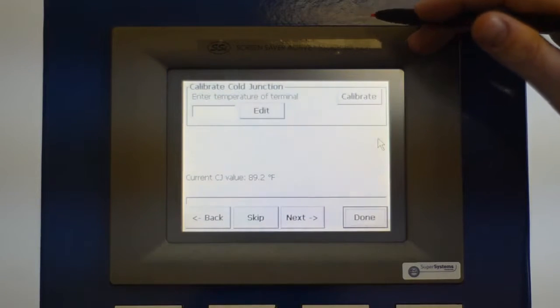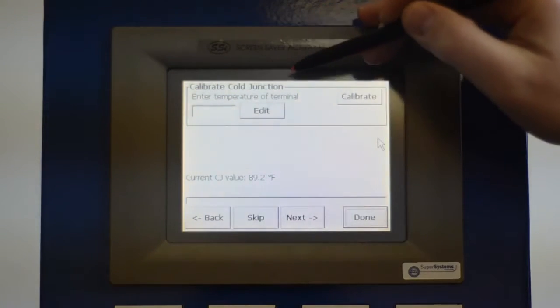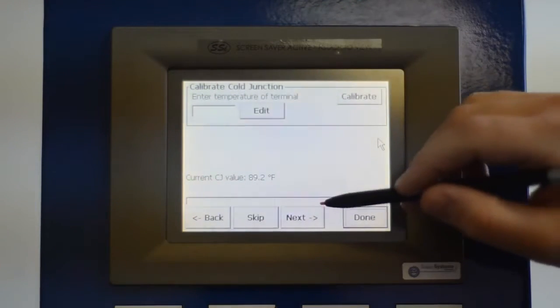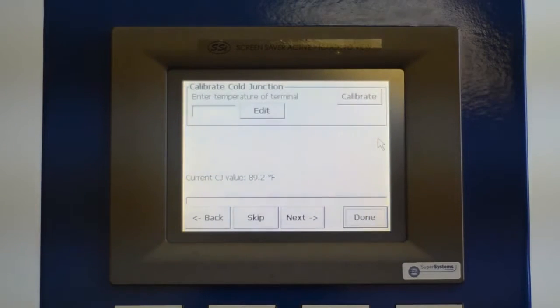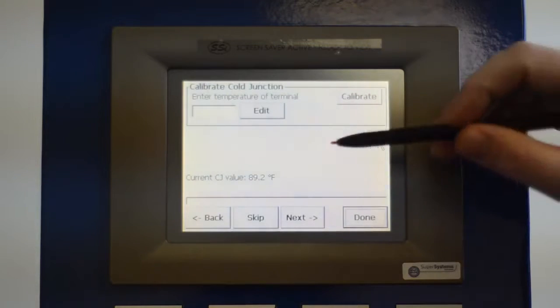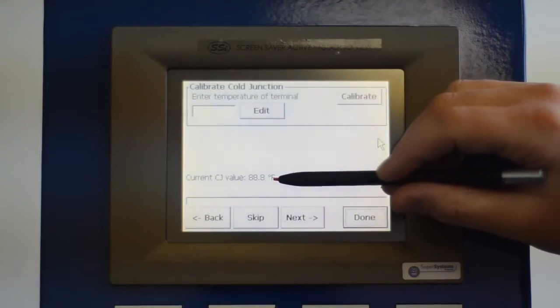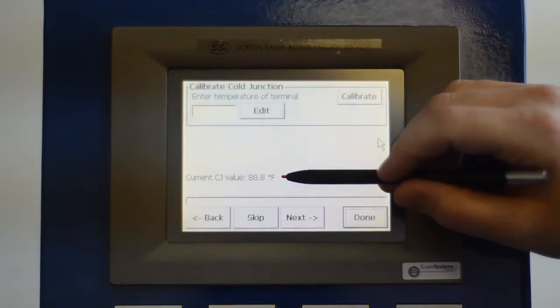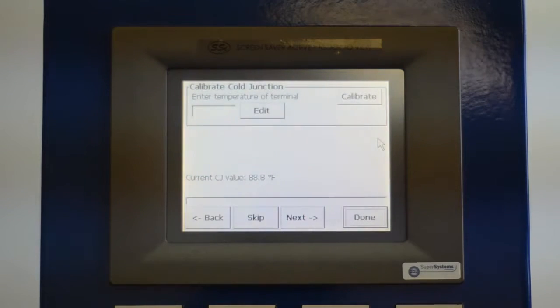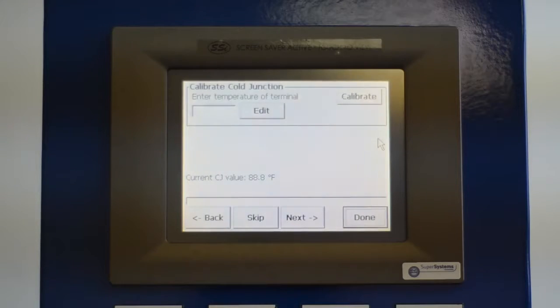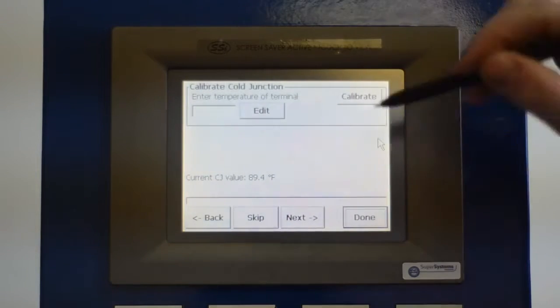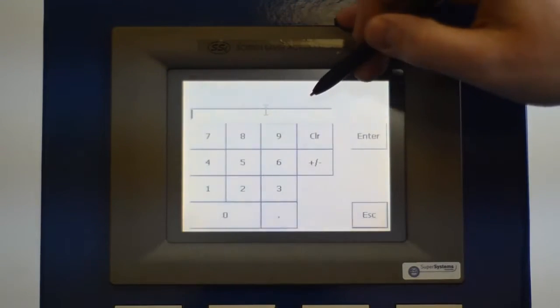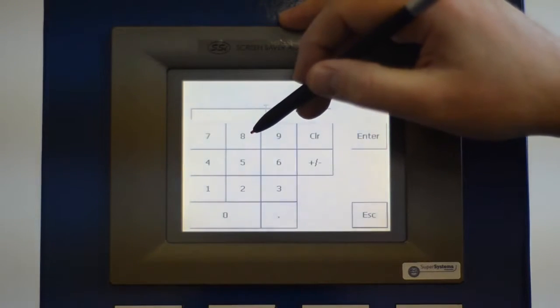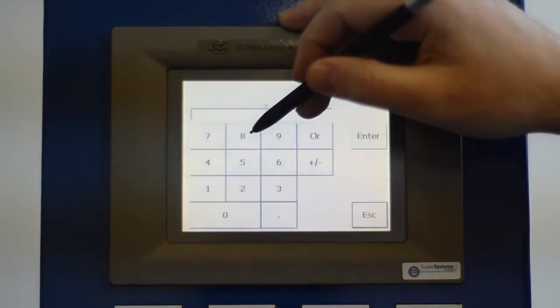And now here, this starts us at the cold junction calibration, so we don't have to go next or pass through any other ranges like we did when we had to perform the zero and span. So it's telling us now the current cold junction value at the terminals is 88.8 degrees. If we did need to make a change to this, let's say that we were a degree high, then we would select the edit button, and we would then subtract that degree high we are from the reading.